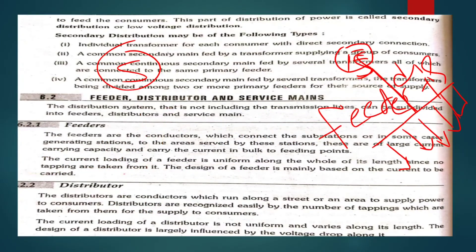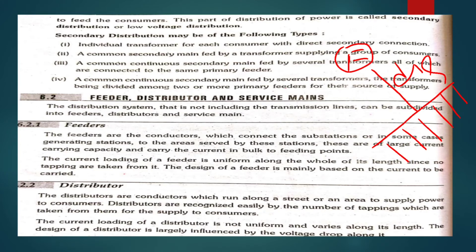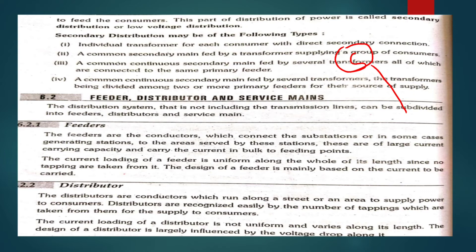Feeders are the conductors which connect the substations — or in some cases generating stations — to the area served by these stations. They are of large current-carrying capacity and carry current in bulk to the feeding point. The current loading of the feeder is uniform along the whole of its length since no tappings are taken from it.